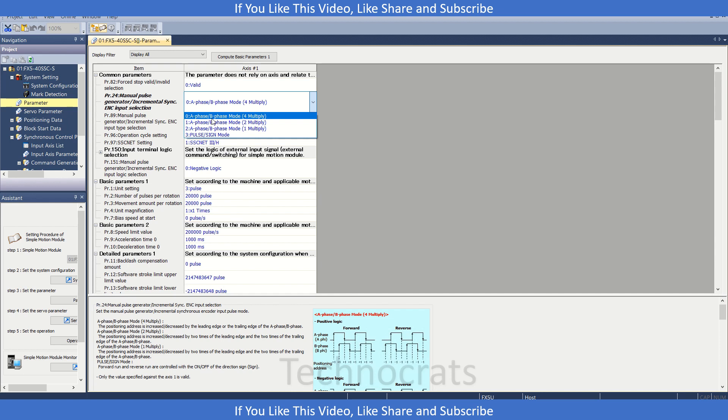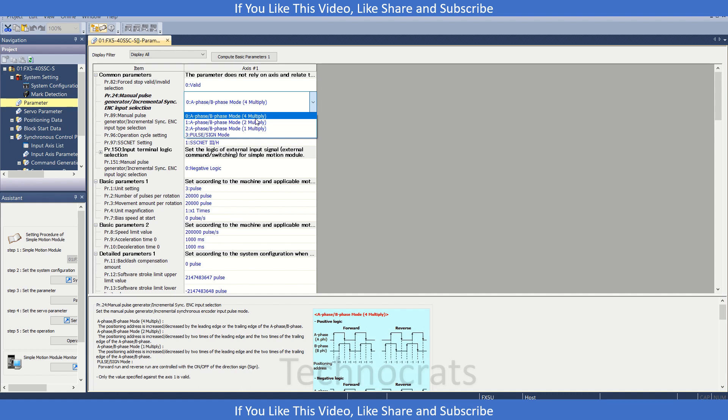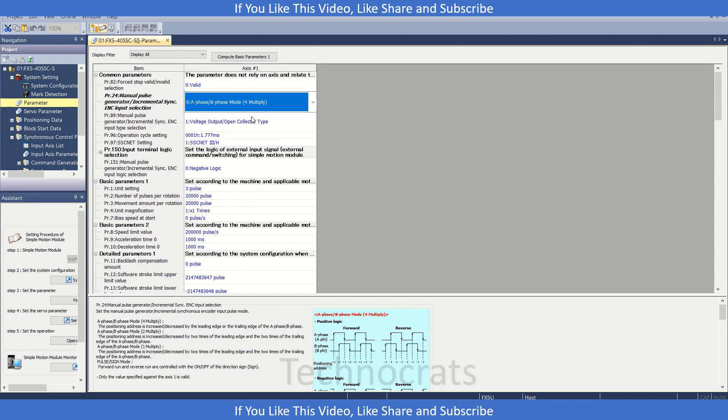We have four options here. First is A and B phase mode: four multiple, then two and one. Then we have pulse or direction sign. In the four multiple, if the encoder is suppose 1024 PPR, then we will get 4096 pulses in the single rotation if we are using four multiple. So basically this will multiply the pulses we are getting from the encoder by four.